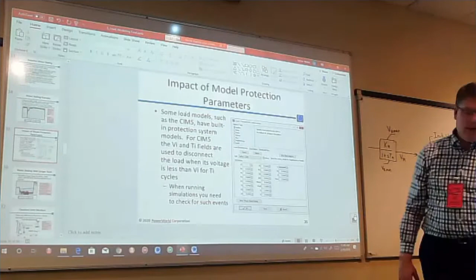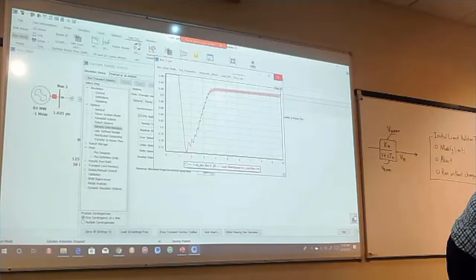Yeah, and this is what this is getting at. So one of the things I could do on this is one of the parameters of a lot of these induction motor models is there's a parameter here that says if the voltage falls below some threshold for longer than a certain number of cycles, then trip. So if I were to change that, I think I'd actually get that to trip, which might prevent the system from. Yep. System goes okay because it just trips the load. Because the voltage dropped too low. So yeah, it's again, at some point you have to model the things that would protect things.